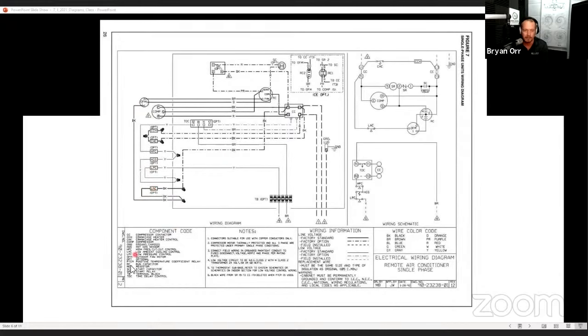All right. So that's the safety circuit. Now let's go through and actually see if we can identify some things. So we're going to scroll to our next. Hold on. All right. Let's pick out some stuff on this furnace and see if we can actually identify it. I could have given more complete pictures here, which may have made it a little bit easier. But let's try to find something. So first thing, let's try to find a fuse. We got our fuse here, and we've got SEC2 and SEC1 connecting right under it.